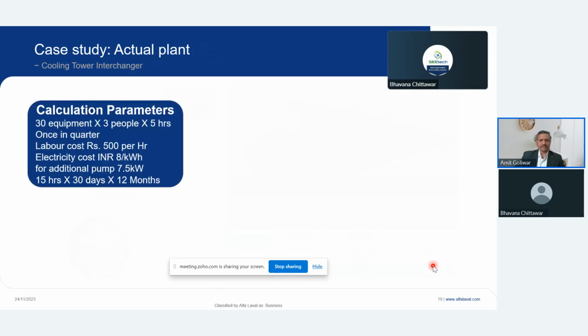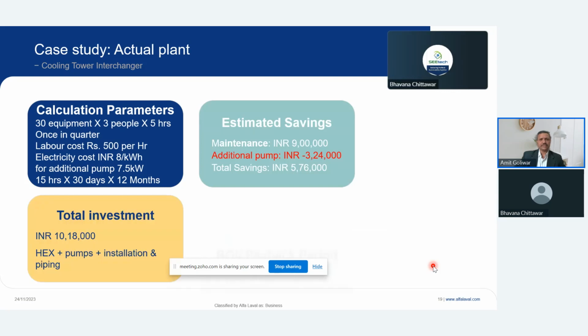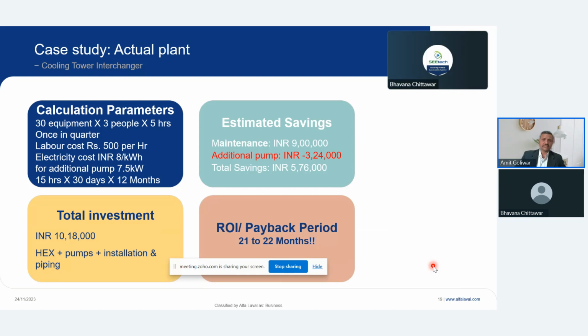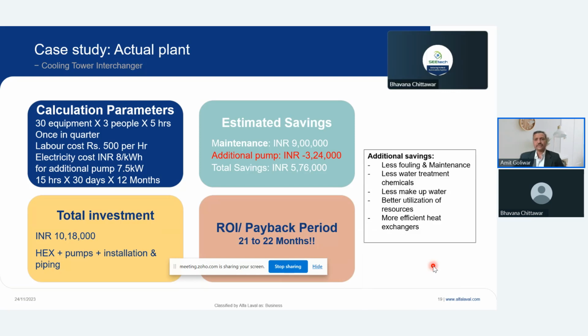To explain even better, if this is a condenser coil tube, and there is a scale, say for example just a 0.6 mm scale inside, the condensing temperature increases, increasing the compressor pressure. And compression ratio is a ratio, and when compressor pressure increases, automatically electricity consumption goes up. So just 0.6 mm thickness can increase the electricity consumption by up to 20%. There are some sample cases where we have achieved savings, wherein there were 30 equipments which used to have a lot of challenges, and there the payback achieved is less than 2 years, with additional savings of better utilization, more efficient heat exchangers, and better control on the plants.